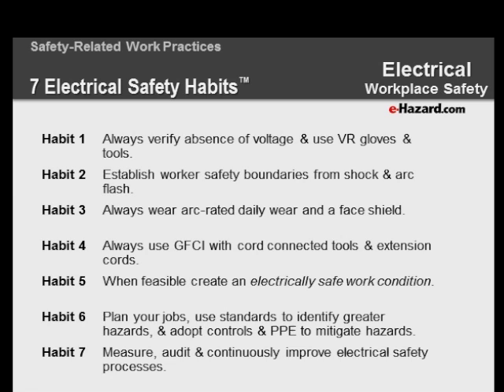It's not required that you wear arc-rated daily wear. It's required that you wear arc flash gear when you're doing the work. But I find that if people, especially electricians and electrical maintenance people, have on a base rating of 4 to 8 calories and wear a face shield when doing any electrical work, most of the injuries and fatalities are gone. Add the other 3 habits, and you'll have a fantastic program that keeps improving all the time.